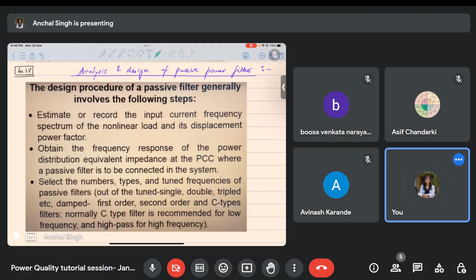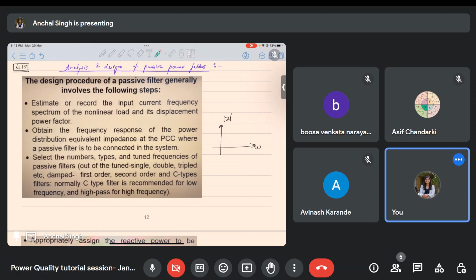Then we obtain the frequency response of the power distribution equivalent impedance, that is, the mod Z versus omega curve, at the point where the passive filter is to be connected in the system. Then we select the number and types of tuned frequencies of the passive filters, and which type of filter we are going to use, whether a tuned filter, a first order, second order, or C type filter. Those decisions we take based on these frequency response curves.